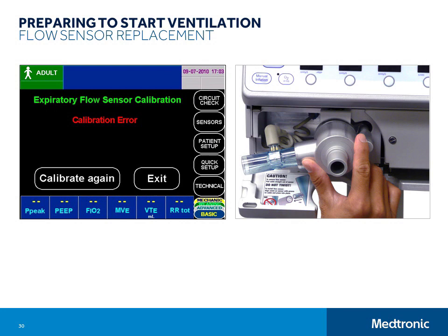Pull the plastic flow sensor away from the outlet of the exhalation valve. Then disconnect the flow sensor cable from the plastic body of the sensor by pulling the cable straight out. Make sure you don't twist it. You can reinstall the sensor by doing the same steps in reverse. When you reconnect the cable to the sensor body, make certain that you line up the sensor port to the notch in the cable connector, then press them together. Make sure that you do not twist while connecting the cable to the sensor. The pass-fail result is logged in the event history. You should also perform the circuit check after installing a new flow sensor.